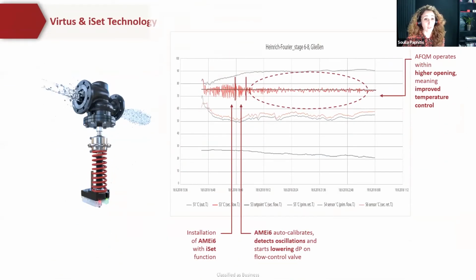So with the use of our latest technology, which is the Virtus PICV, and autonomously controlled intelligent actuator, which is the ISET, you have the ability to change the differential pressure over the motorized control valve. And this ensures flow stability for high and low flows, and with the added benefit of having a more compact design and added setting indicator. The split characteristics of the Virtus PICV offers improved control and higher accuracy. The intelligent differential pressure adjustment ISET actuator improves network efficiency by offering continuous auto commissioning and providing pump cost optimization, and can offer predictive maintenance when it's being monitored.